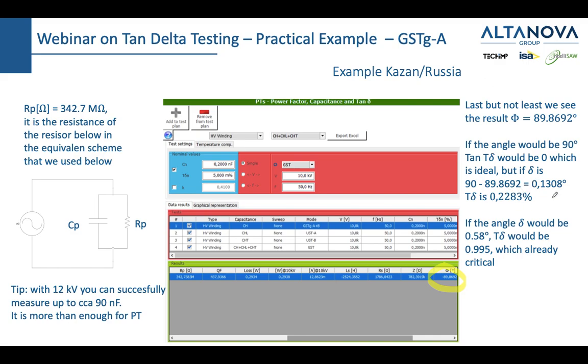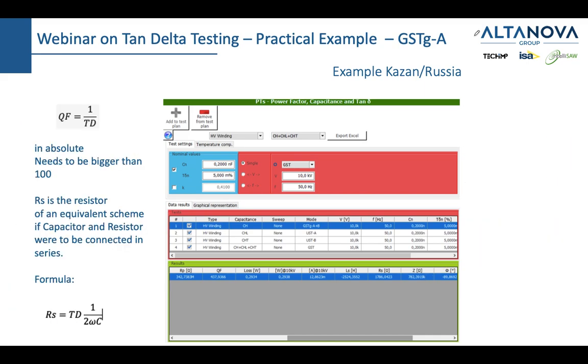0.2283%. So let me just tell you that if your phi would be smaller than 89.42, you would have a tan delta bigger than 1. This just goes to prove how small that angle is allowed to be. Or if we talk about Hans Brinker and the story about the dike, how small the leak can be to destroy the whole dike.